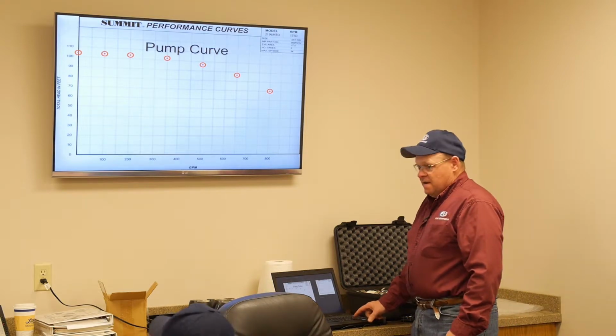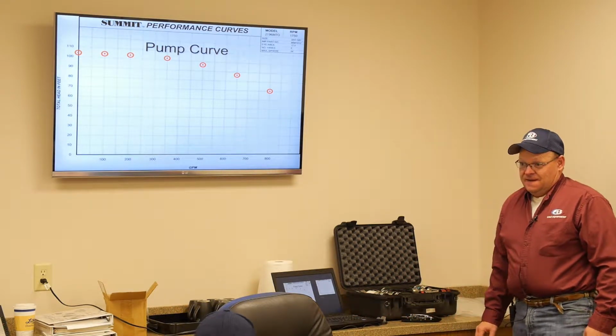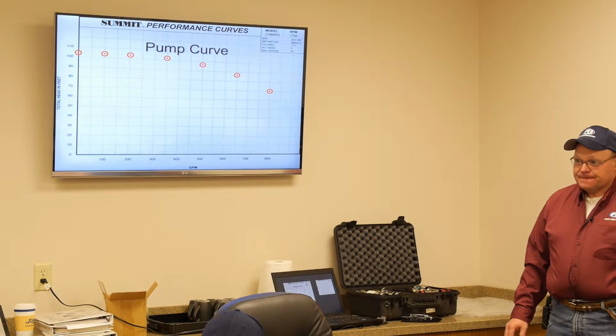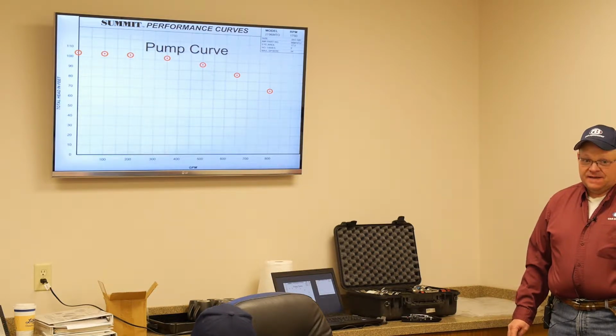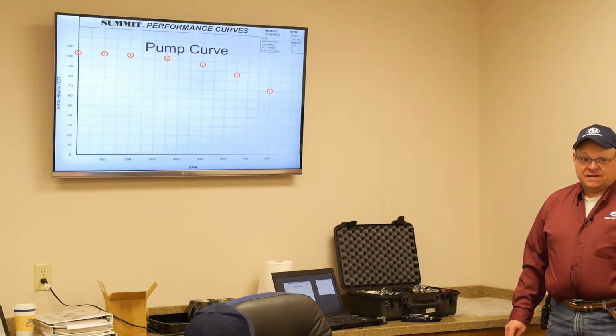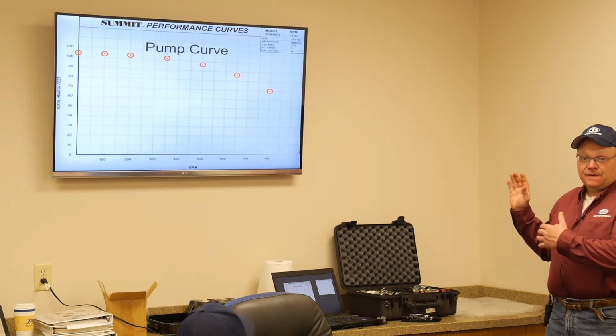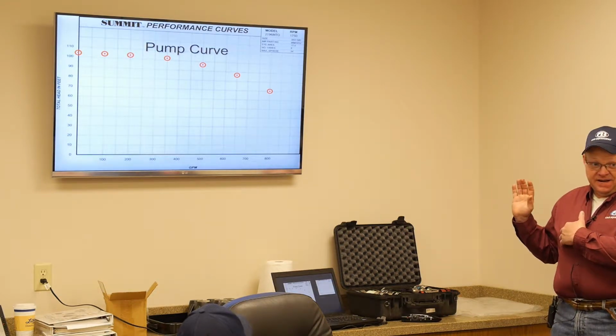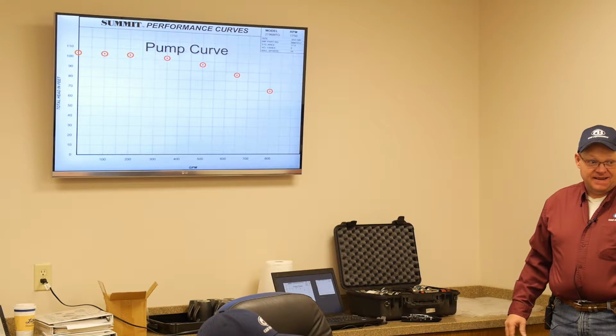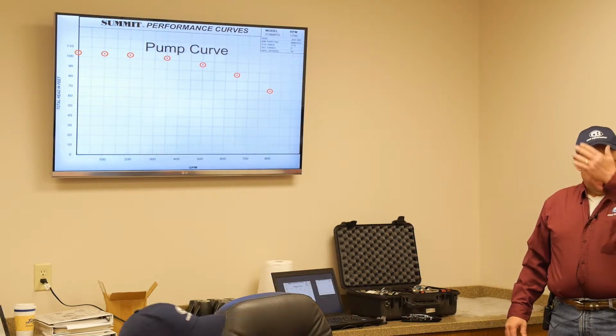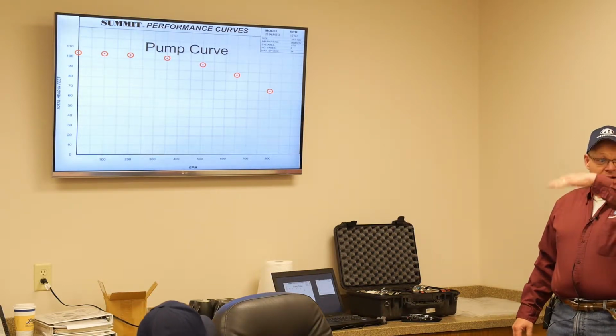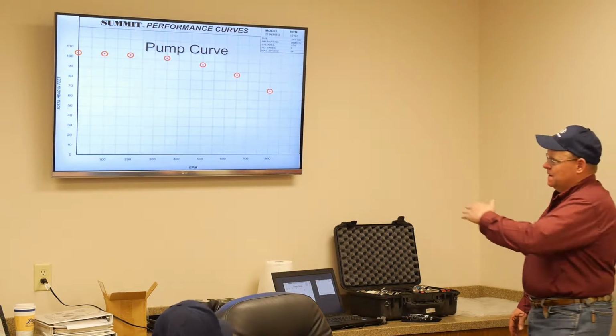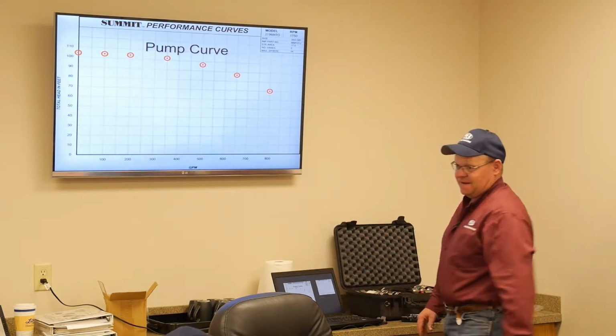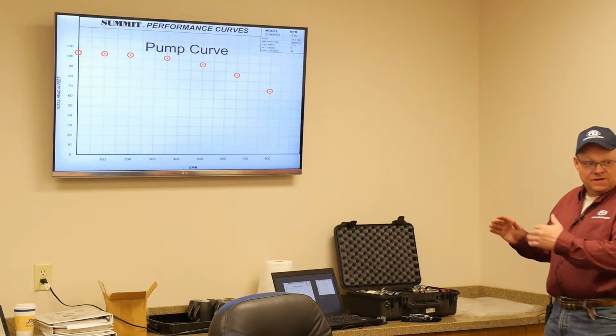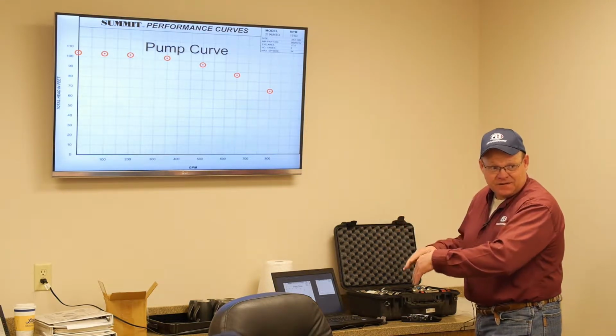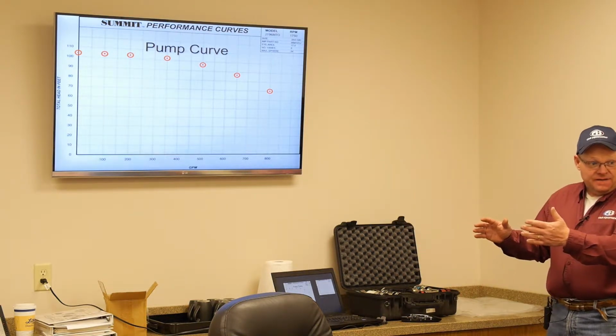And all that is determined by the system. Not by the pump, but by the system. Because remember, this is a pressure creating device. So if your system changes, your flow and performance is going to change. Your tank gets full, and your head pressure's going to go up, right? As your tank gets full, you're moving to the left. So it's going to take longer towards the end of that batch to get it off.